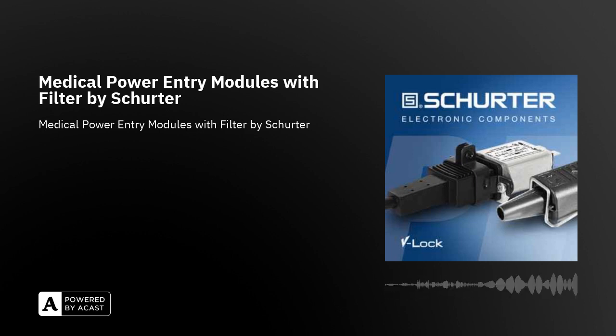Filter, energy stored in capacitors. If you unplug the power cord from the outlet, the voltage from the capacitors is present on the power pins until the capacitors are discharged. The requirement is 1 second after unplugging the power cord, the voltage on the pins that can be touched by the operator must be a maximum of 60 volts. The Schurter solution is PEM with a bleeder resistor between the phase and neutral conductors.